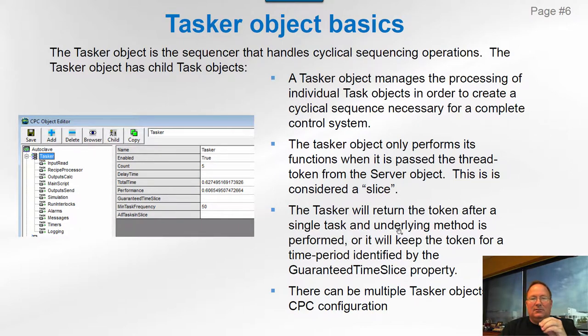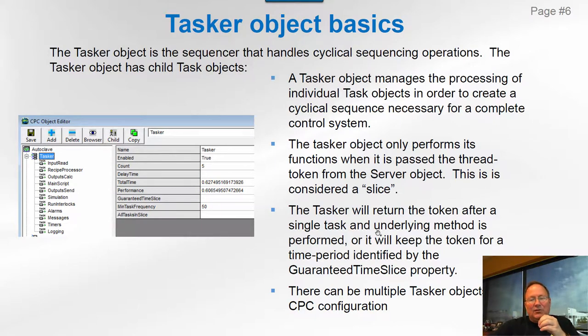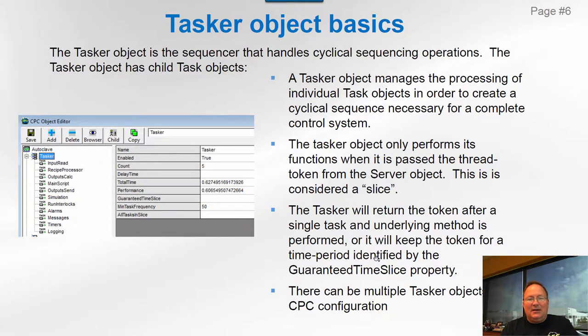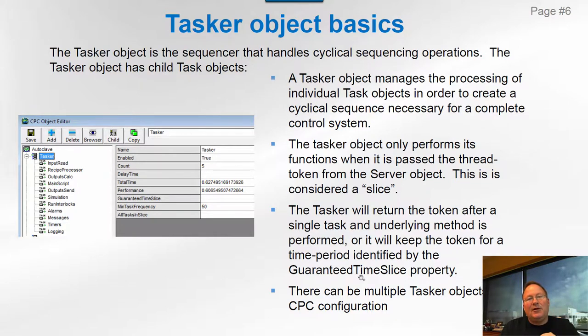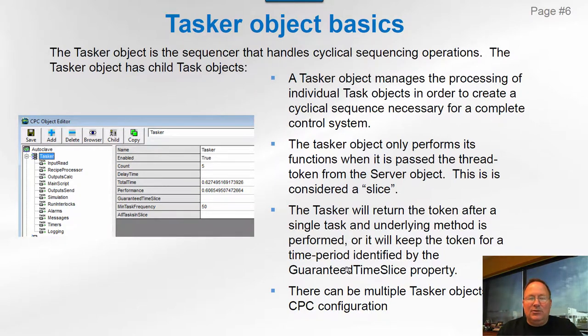The tasker will return the token after a single task is completed, or whenever one of the underlying sub-method calls is completed. You can set guaranteed time slice to increase the amount of time that the token stays with that tasker — a way of really speeding up taskers — but it will also create hangs in your client; it'll seem sluggish. Typically we don't use guaranteed time slice, but if we do, it'll be a very small number like 0.001 or two milliseconds. If you make it too big, you'll see problems with your clients.